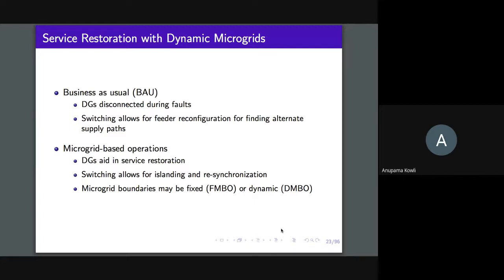The idea was simple. If we were to do usual service restoration, during a fault all distributed generation would be de-energized, and then you'd have de-energizing of the feeder, isolation, and rerouting of power, as we discussed at the start of this talk. If we were to do microgrid operations instead, distributed generation need not be de-energized—it will continue to service loads within its microgrid boundary, and we'd exercise switching. Islanding would be used to either contain a fault or exclude its impact.